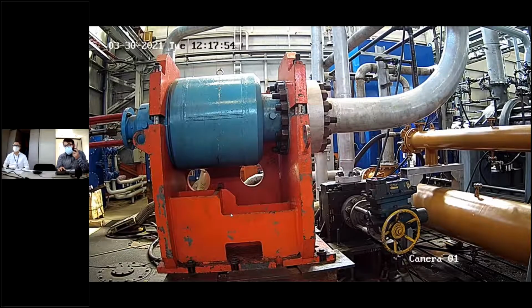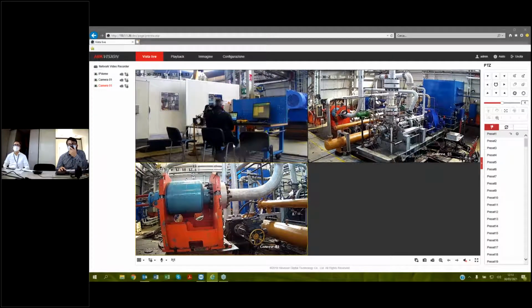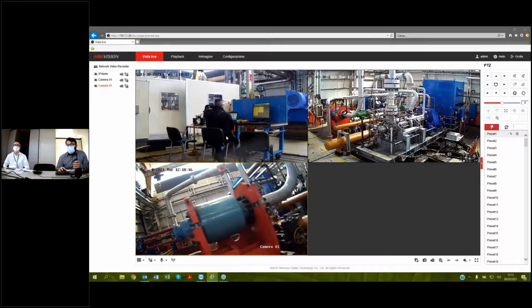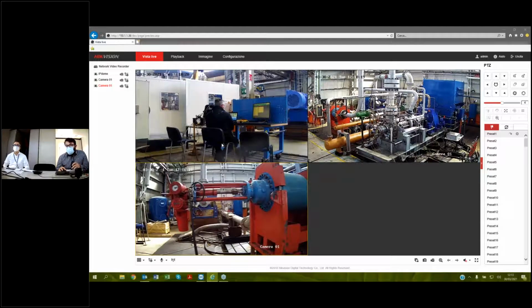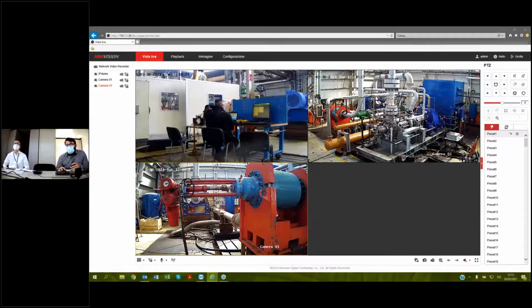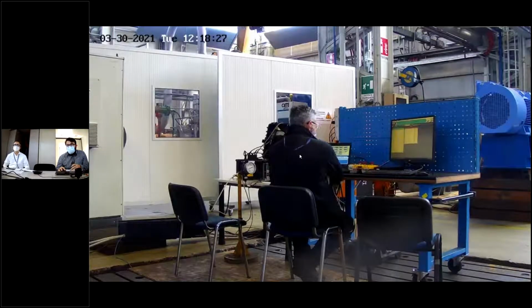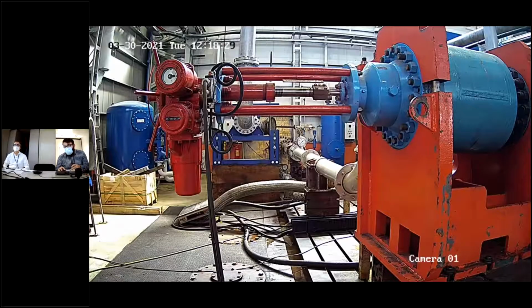Okay, now on the video you can see the details of the two valves to regulate the capacity. On the left we have the main valve for the discharge line, on the right the bleed off valve. To control the flow, we can operate the valve using a manual control directly on the test bench. After the valve, the water goes in the discharge line where the two flow meters are installed to measure the capacity. There is a flow meter for the discharge line and one flow meter for the bleed off line.